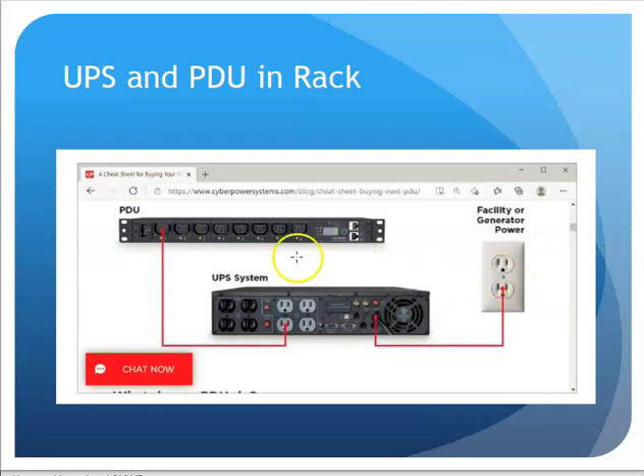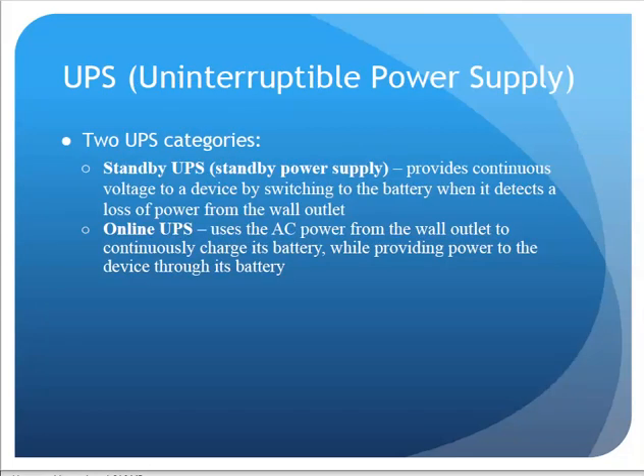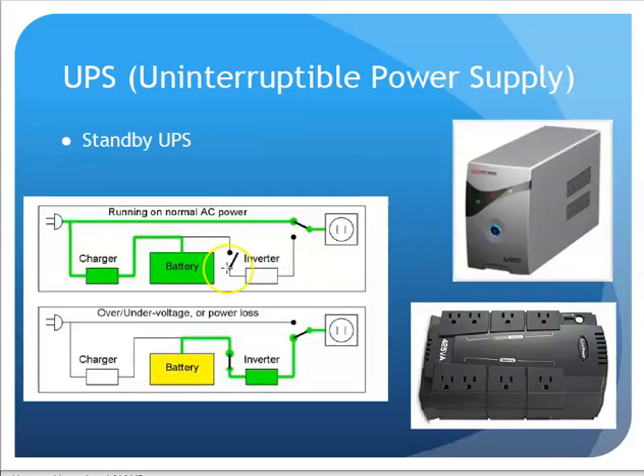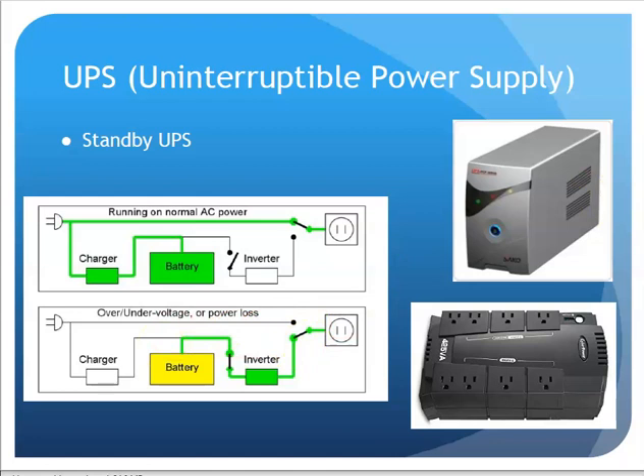A typical arrangement has power coming through a UPS into a power distribution unit. There are two types of UPS units: standby and online. A standby UPS is just waiting for the power to go out — when it senses signal loss, the battery kicks in, doing a mini switchover from normal power to battery. Most home UPS units work this way, and usually it works okay because it senses the loss and switches over very quickly.